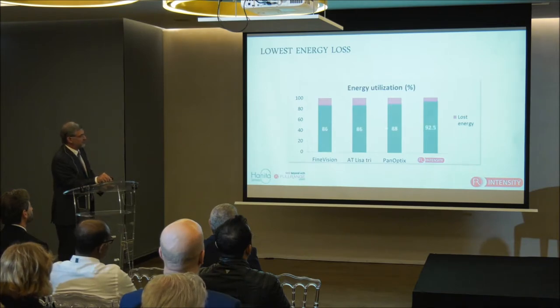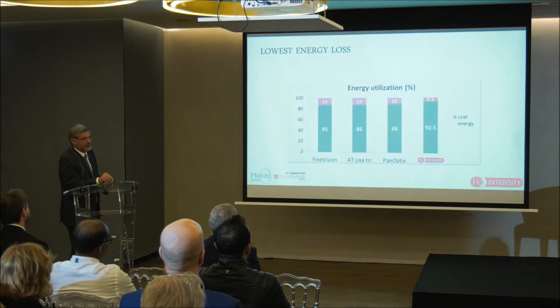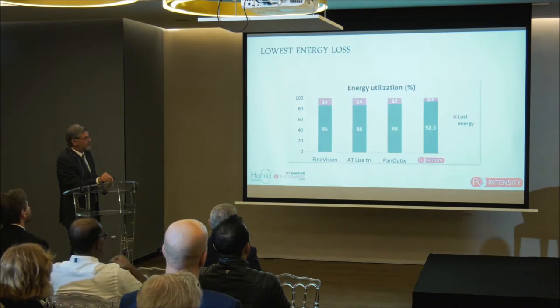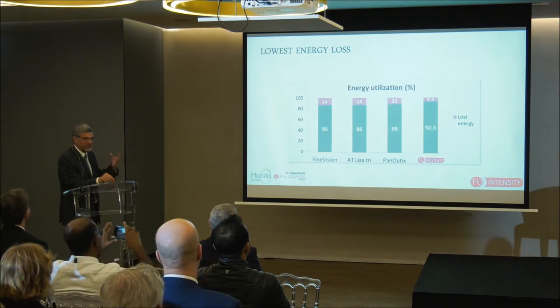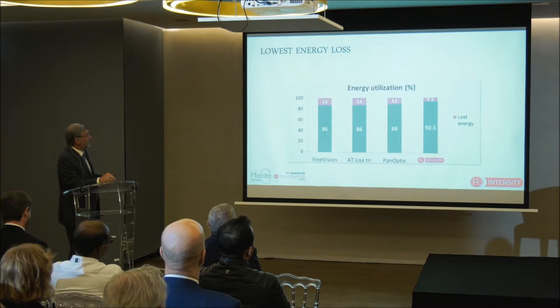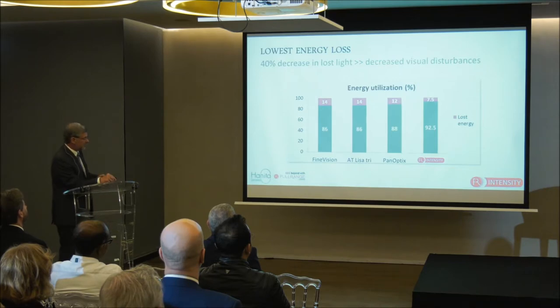In comparison to other lenses — Fine Vision by PhysIOL, AT LISA by Zeiss, PanOptix by Alcon — versus the Intensity by Hanita: competitor lenses direct approximately 86–88% of light to the foci, losing 12–14%. The Intensity directs 92.5% to the desired foci, losing only 7.5%. That may not sound impressive, but consider: 14% lost in the others versus 7.5% in the Intensity — nearly half the light loss. This 40% reduction in wasted light directly reduces the halos and glare associated with these lenses.